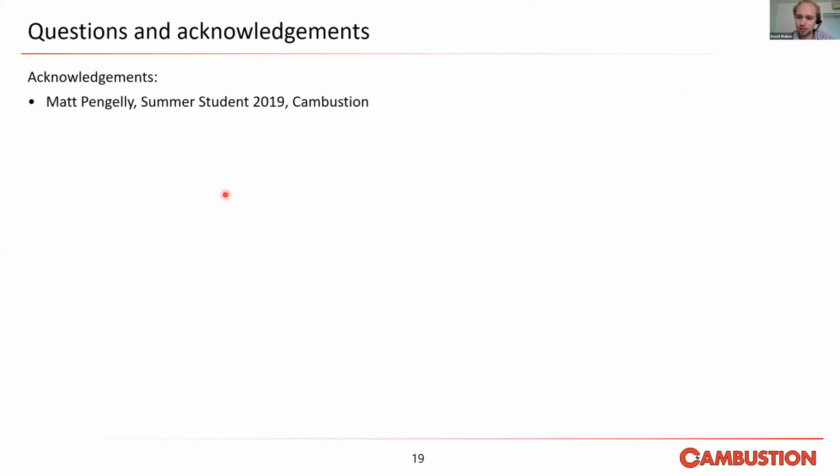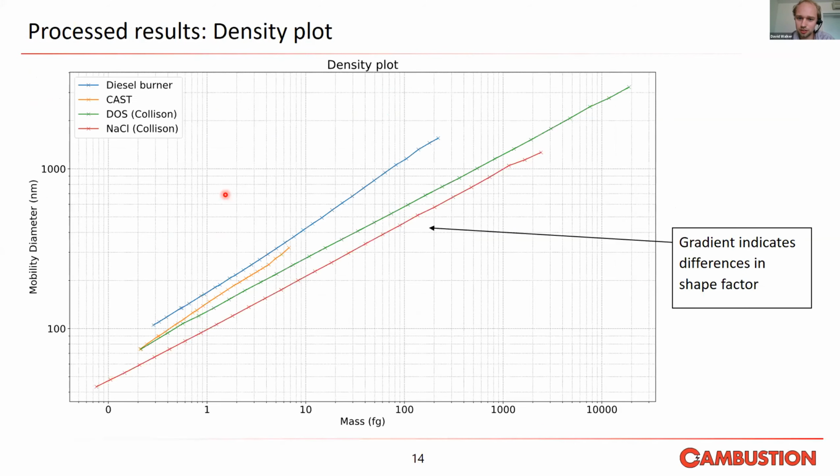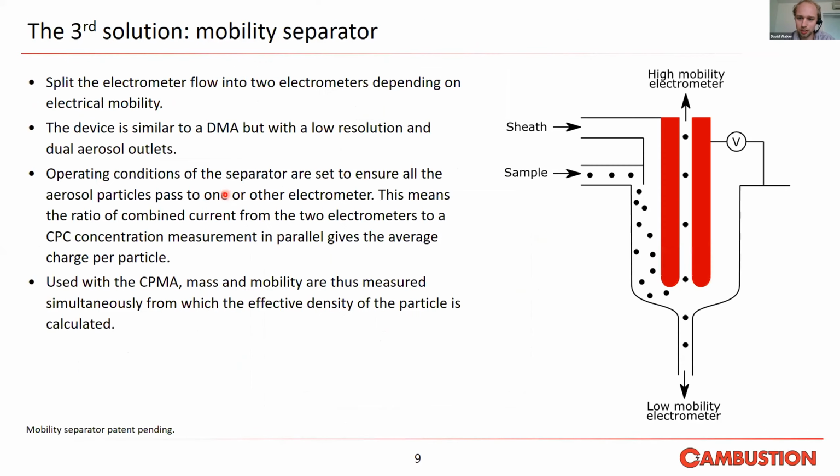Hi, I had a question about the particle losses to the walls. If they're charged, would that create a surface charge on the instruments? So this is presumably back on the mobility separator. So the idea is there are no particle losses through this, because by careful selection of the flows, and because this is effectively a monodisperse aerosol coming in, the particles are drawn into this clean sheath flow, but they never make it as far as the wall.